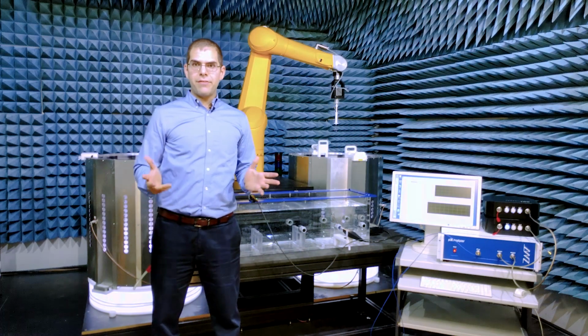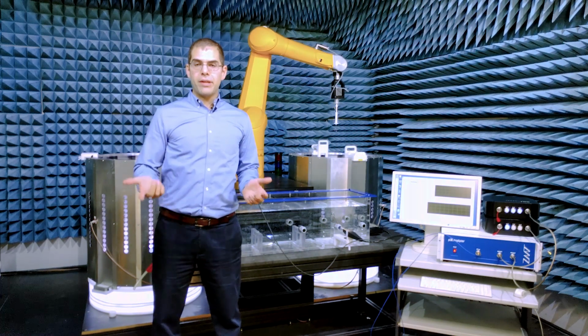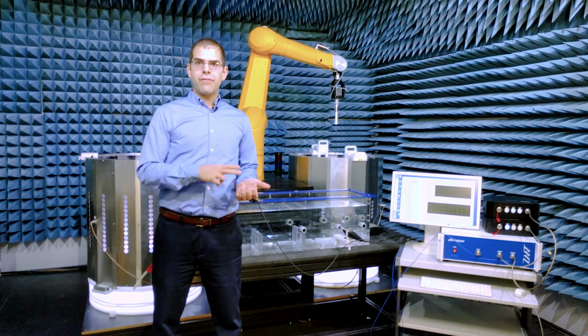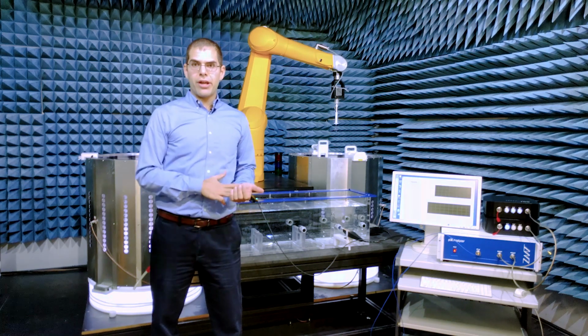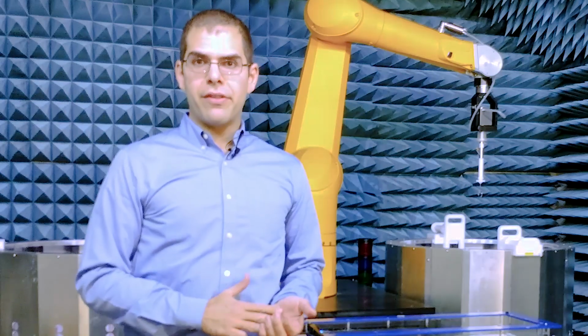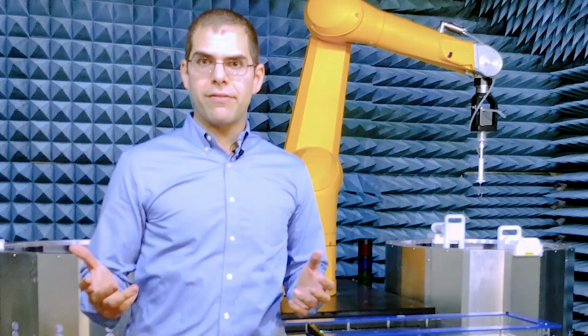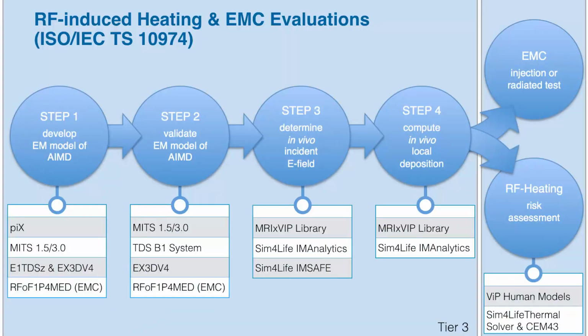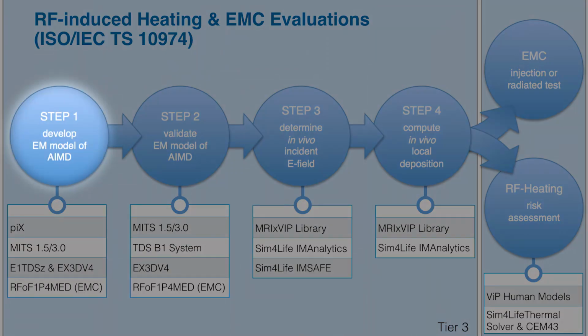The goal of this kind of safety testing is to show that the implant is safe for every person, for every position, in every kind of MRI scanner. That's a big job, but the Tier 3 approach of ISO 10974 splits it into smaller problems that we can solve one at a time. Step 1 is to create a model of how the implant responds to fields when immersed in tissue simulating media. That's what I'll show you today.